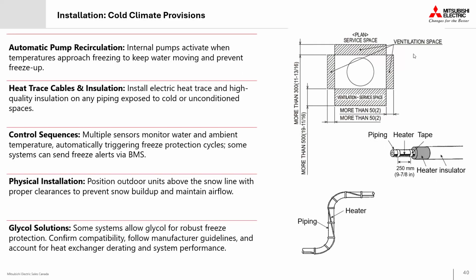So in terms of installation considerations for our cold climate here in Canada, there's a few different strategies that we usually see leveraged on a lot of our projects here in Canada. When installing these heat pumps in cold climates, it's important to consider provisions for freeze protection and long-term reliability. So for systems that are not using glycol in the primary loop, adding insulation and heat trace to our exposed piping can be an effective way to guard against freezing within that primary loop, especially on those outdoor runs between the outdoor unit and the building.